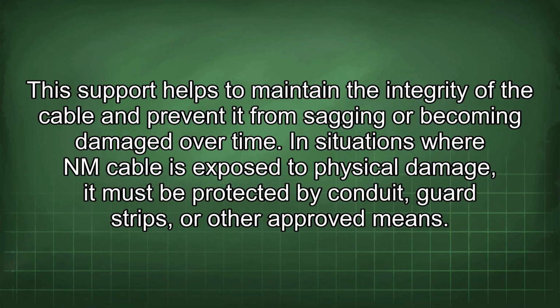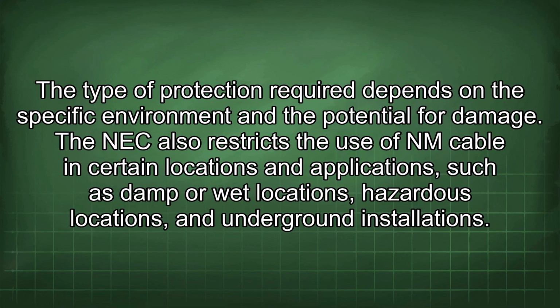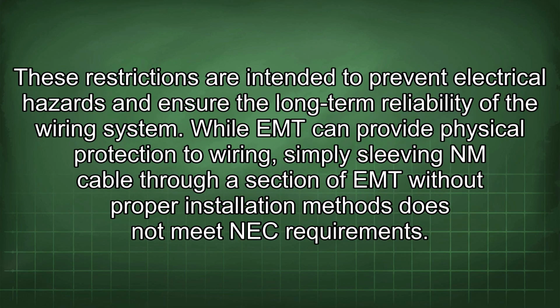In situations where NM cable is exposed to physical damage, it must be protected by conduit, guard strips, or other approved means. The type of protection required depends on the specific environment and the potential for damage. The NEC also restricts the use of NM cable in certain locations and applications such as damp or wet locations, hazardous locations, and underground installations. These restrictions are intended to prevent electrical hazards and ensure the long-term reliability of the wiring system.